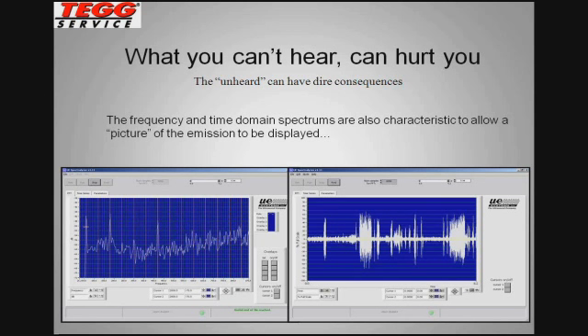If you look at frequency, and assuming we are on 60 hertz systems, we're going to put a 60 hertz harmonic cursor on the spectralizer. And what we traditionally see is the first couple of 60 hertz harmonics. And what a harmonic is, for those not familiar, is a multiple of the base frequency. So if you're on a 60 hertz system, the second harmonic would be 120 hertz, the third harmonic would be 180 hertz, and so on down the line.